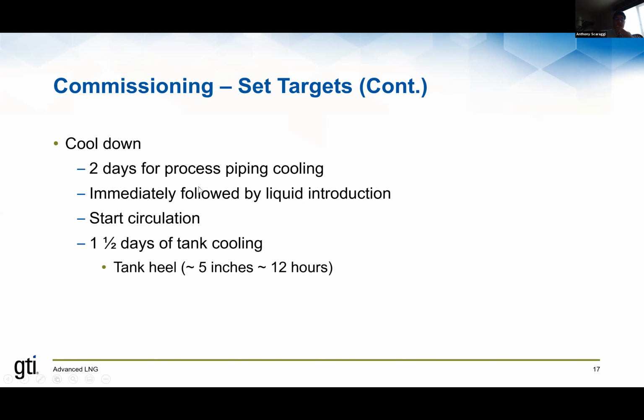So this is typical for, let's say, a line from the facility to the dock, where you would either receive LNG and pump it into the tanks, or you would take LNG from the tanks and deliver it to a ship for export. That piping system would fall into this category, where initial cool down would take about 2 days, give or take. It depends on a lot of other things, how long the pipe is and such. But as an average, 2 days. And then you immediately introduce LNG into that system once it's properly cooled down, and you continuously circulate LNG through that unloading line to maintain it at its cold temperature.